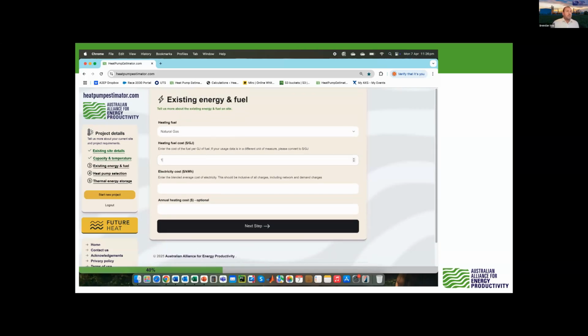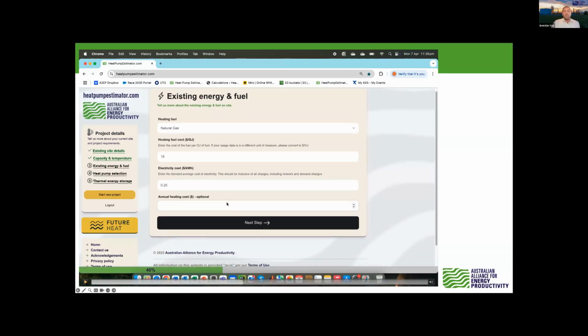And now we go, what are we costing for our gas? Let's call it $18 a gigajoule and 25 cents a kilowatt. On this option here, if you do know your annualized heating cost, then I'll pause. You can enter that and it will use that, providing you're not wildly away from what our load profile calculates and what our system efficiency number is in the background. Because sometimes you'll get a gas bill, it won't be broken down as granularly as it probably needs to be. We did talk about metering before. If you had very accurate metering, you could type the number in and we would run off that number. It would let that number through.